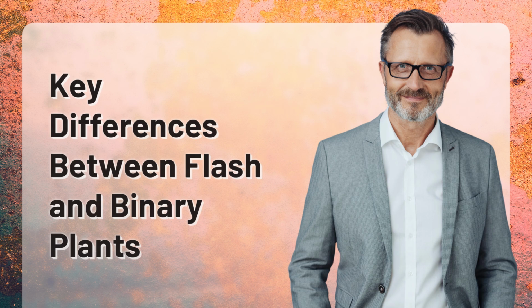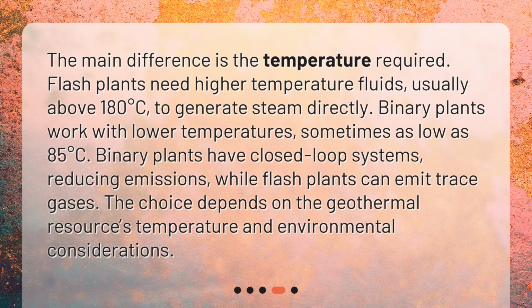Key differences between flash and binary plants. The main difference is the temperature required. Flash plants need higher temperature fluids, usually above 180 degrees Celsius, to generate steam directly. Binary plants work with lower temperatures, sometimes as low as 85 degrees Celsius. Binary plants have closed-loop systems, reducing emissions, while flash plants can emit trace gases. The choice depends on the geothermal resource's temperature and environmental considerations.